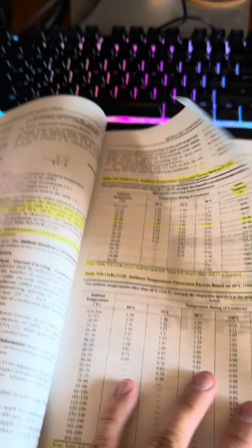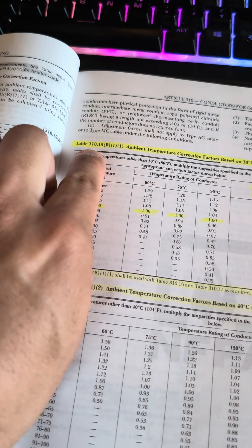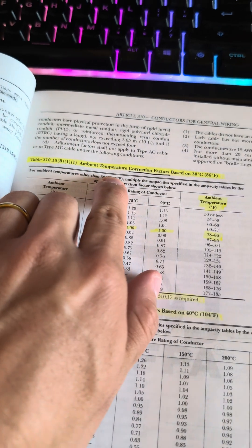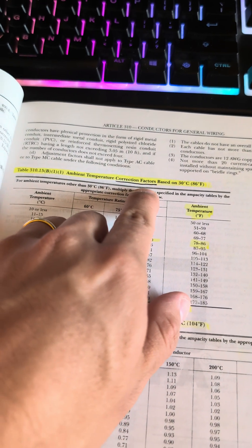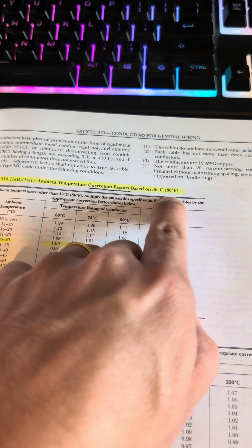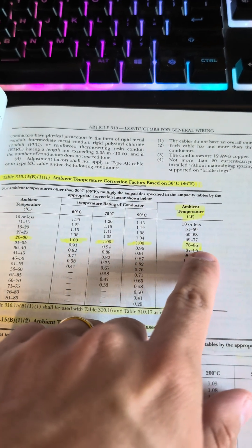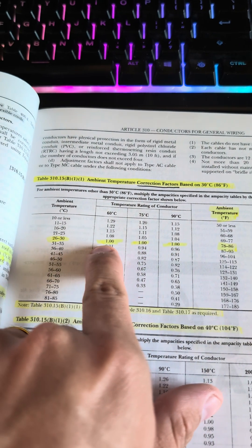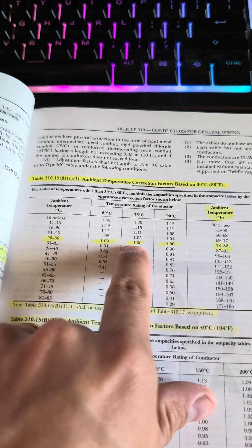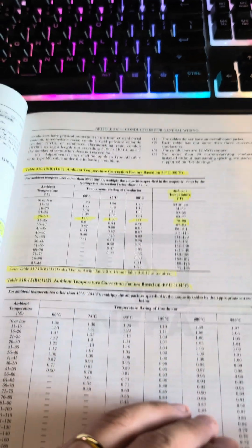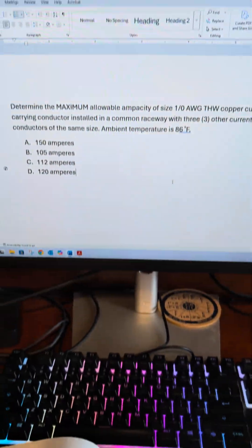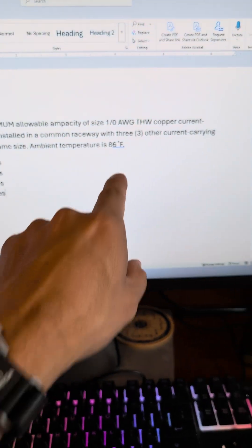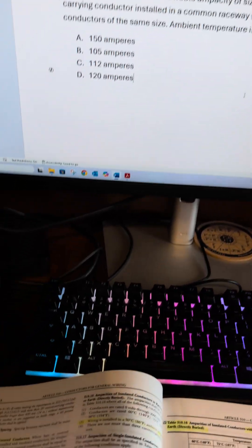If we look at Table 310.15(B)(1), this is the ambient temperature correction factor. It's based on 86 degrees Fahrenheit, and if we look, the multiplier for all three columns is times 1.0. Anything times 1 is itself, so technically we don't really need to correct, but if this ambient temperature was different, we would need to.